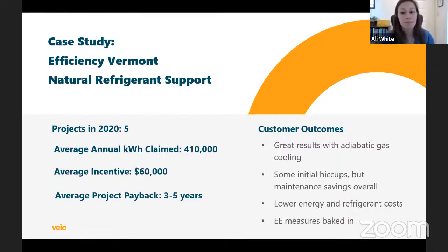I've seen great results with adiabatic gas cooling, and on 2 of the projects, they've been able to avoid going into supercritical mode at all in the summer using adiabatic gas cooling. And that is still impressive in Vermont because, as I mentioned, it's very humid. And a lot of those energy efficiency measures are baked into the design of these systems, and that makes calculating the energy savings and getting utility support even easier.